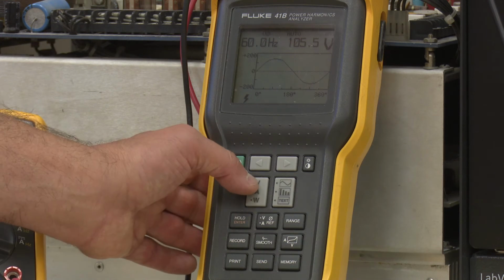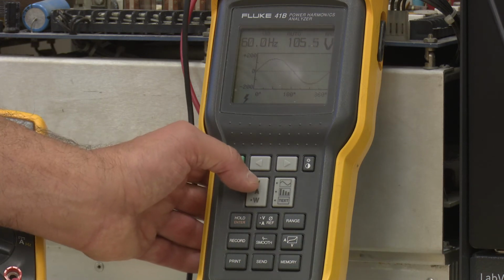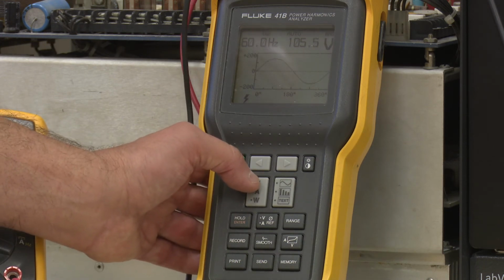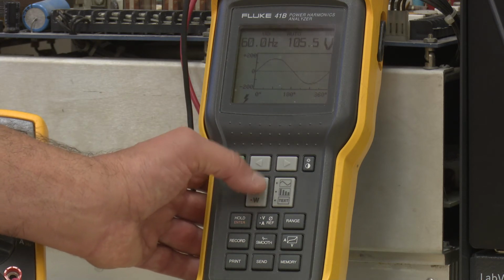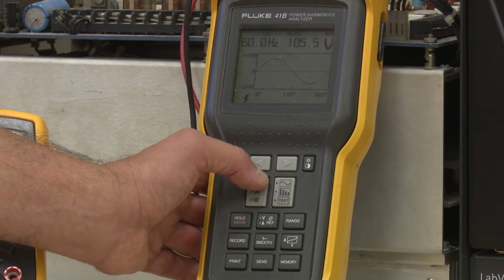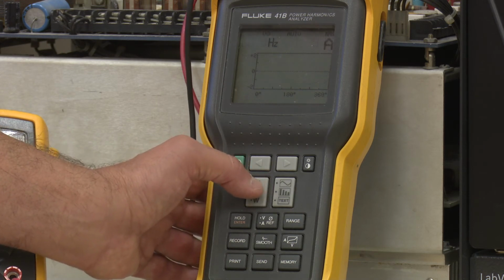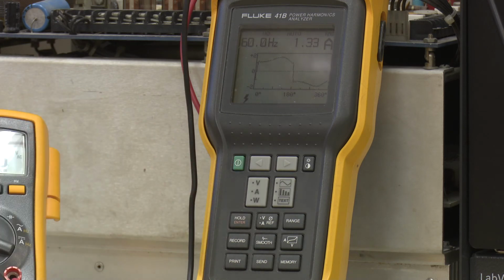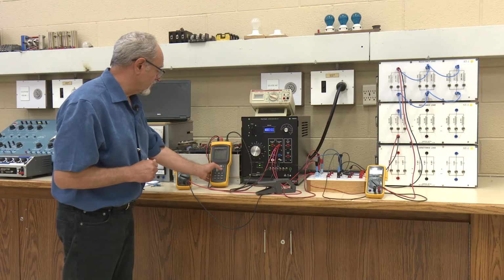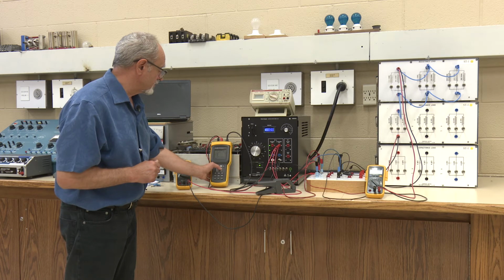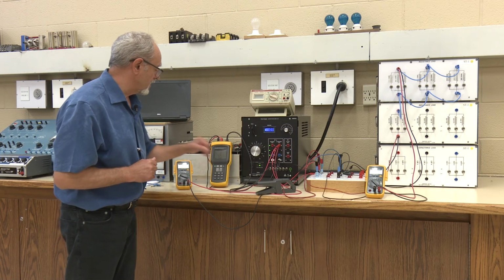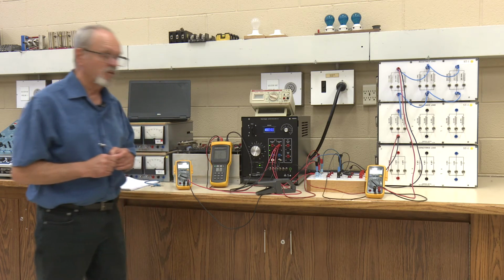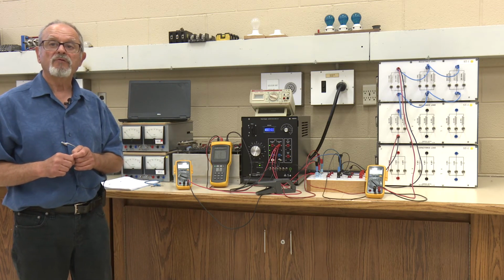And this time, if we go to our Fluke analyzer, we'll see the AC waveform for the voltage still looks like very little distortion, but the current on the line side is severely distorted. In fact, if we want to see how much distortion the current is actually experiencing on the line side, it's 31.5% distorted away from a pure sinusoid.